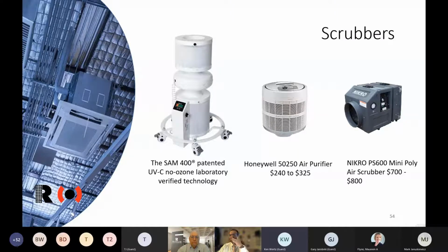These require maintenance, so hopefully these will come out of circulation after the COVID issues go away, and we can put them in a storage container potentially for the next pandemic. But just make sure that you're doing your proper maintenance on them. They need filters. They need to be cleaned. Don't go and store them with dirty filters in them. Be smart about it. Do you know how many you have? Can you get new filter media? All that kind of stuff.